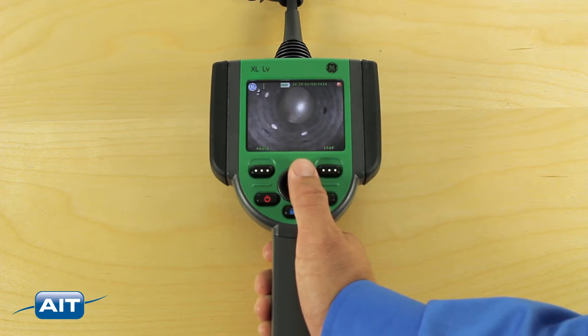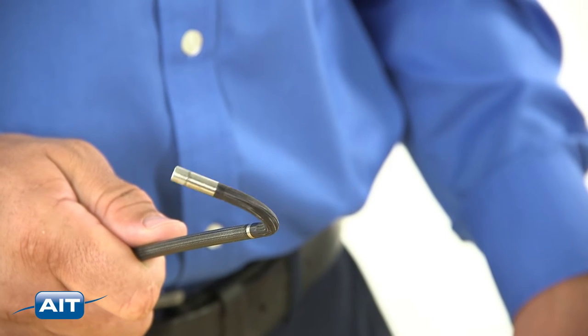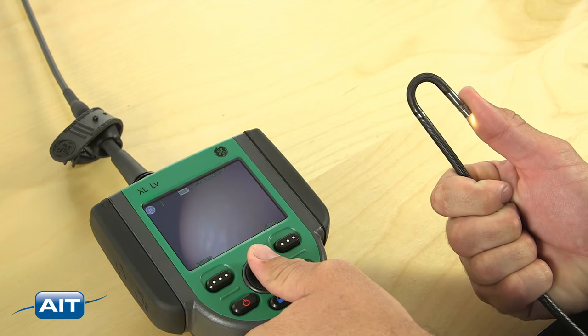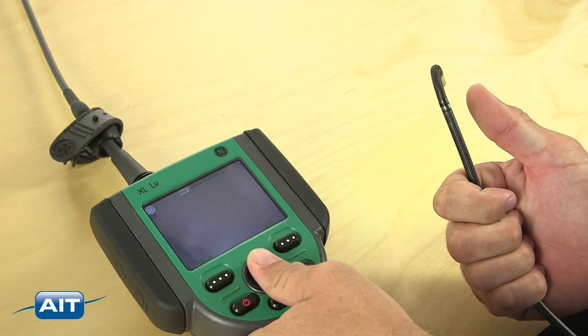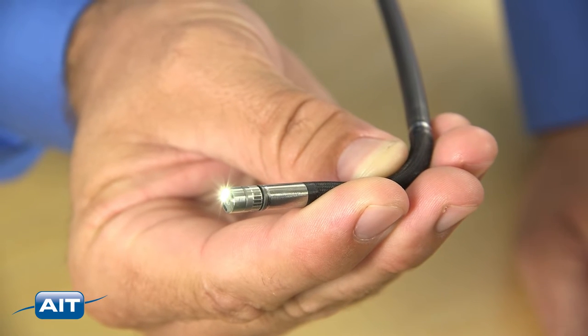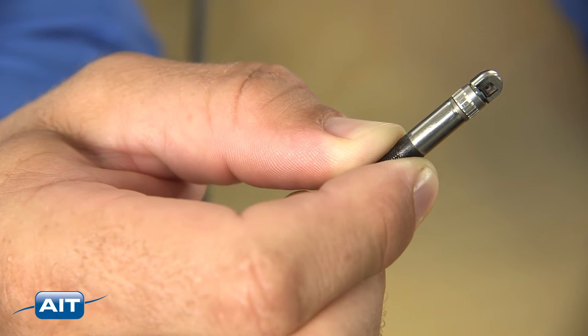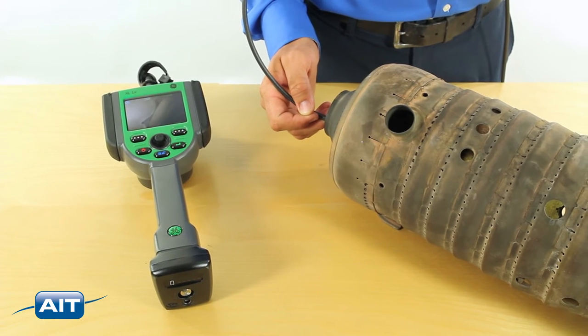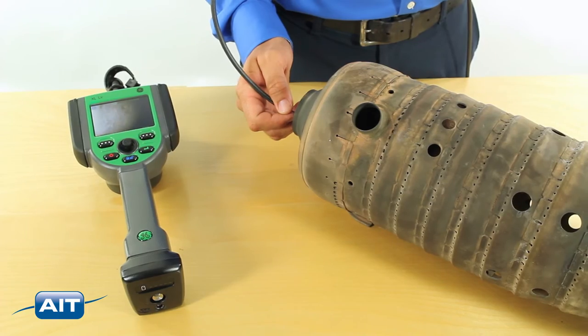The XL-LV offers servo control all-way joystick articulation, which is superior to mechanical articulation and protects the system from over-torque, a common source of damage on other video borescopes. The only video borescope in its class that has a true selection of forward and side view tip adapters with secure double threads. Other video borescopes in this price range are typically fixed forward view, which limits their usefulness.